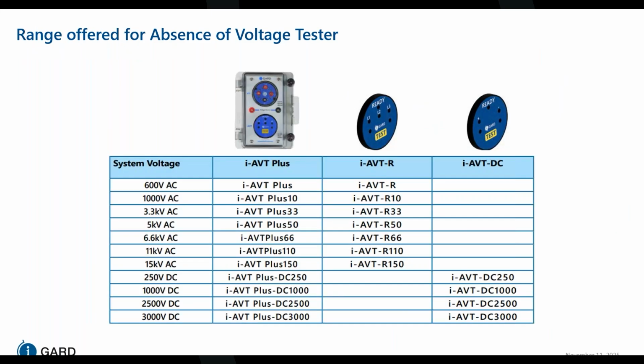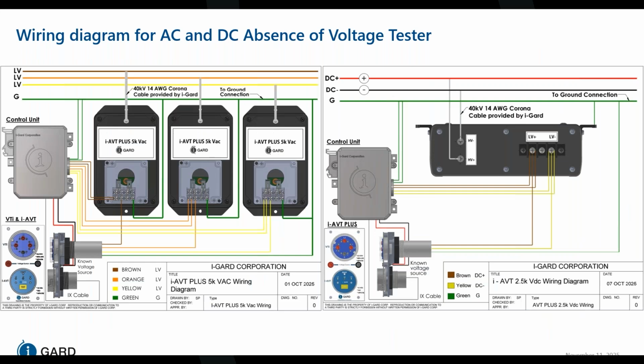Our absence of voltage testers come in different models to handle a wide range of electrical systems. Whether you work with AC or DC power, we have options for voltage from 600 volts up to 15 kV in AC, and in DC variations we have 250 volts DC up to 3000 volts DC. This slide provides a typical wiring diagram of a 5 kV absence of voltage tester for the AC system on the left side and a 2.5 kV version for the DC system on the right side. So this will give you a little bit of an idea on how the absence of voltage tester gets connected into the system.